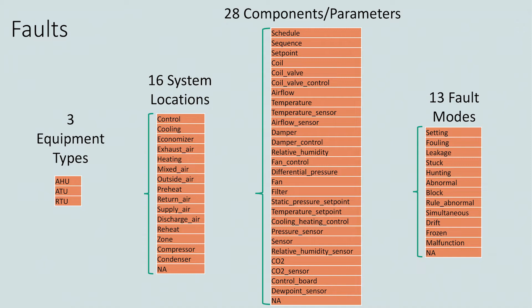Now for the components or parameters, I think this is important in terms of communicating what FDD tools do, given they don't always fully diagnose and point you to the exact cause. In some cases you can tag a fault to a component — a mixed air temperature sensor demonstrated to be constant at a temperature of 200, for instance, is definitely something wrong with that sensor that needs to be looked at.